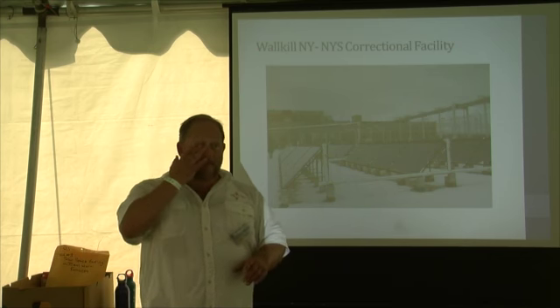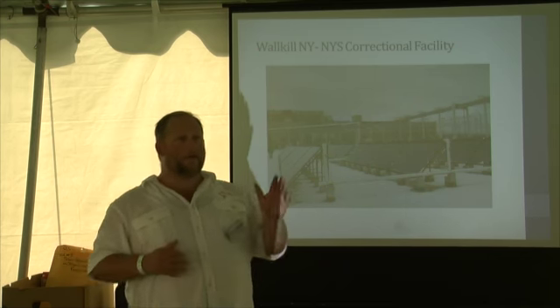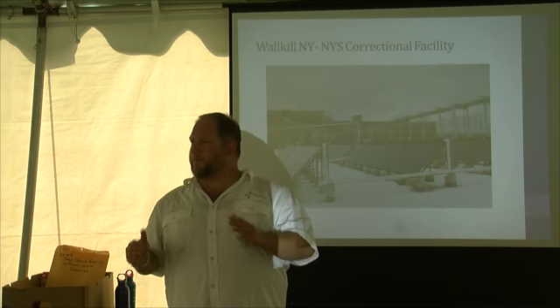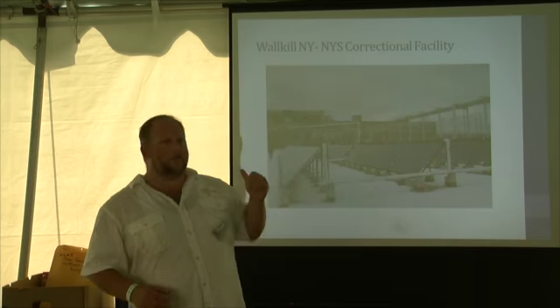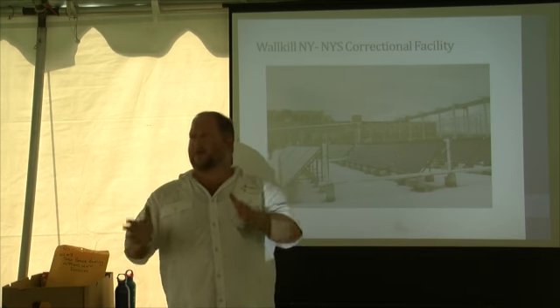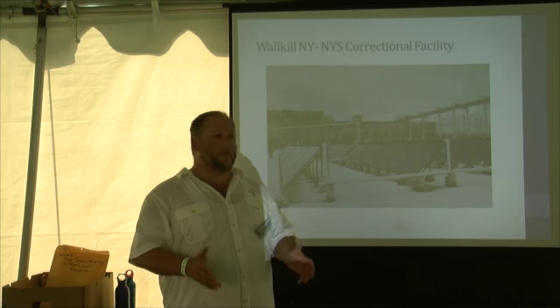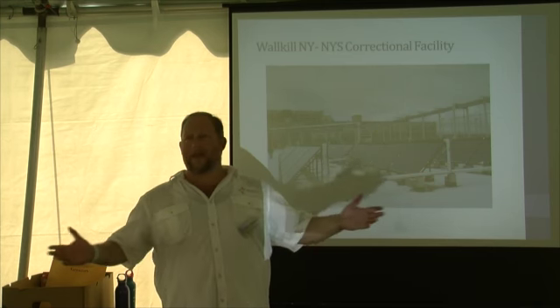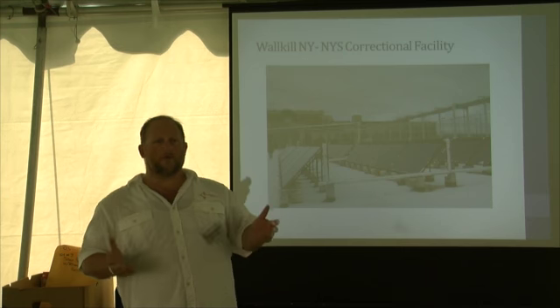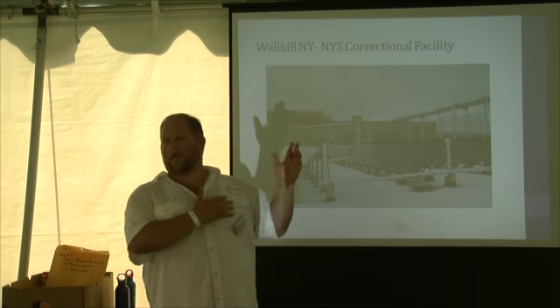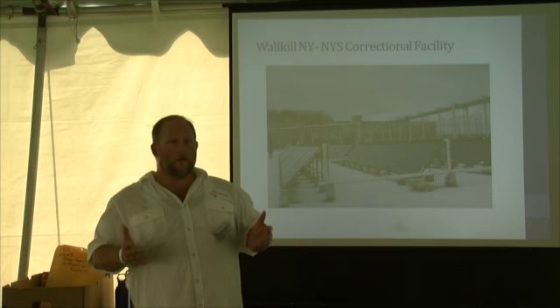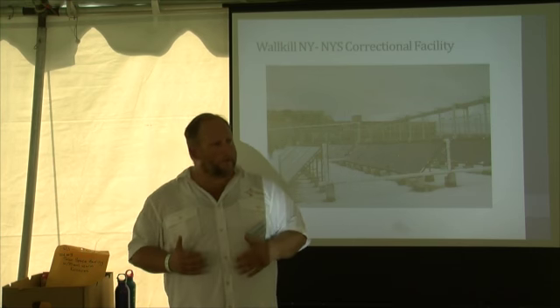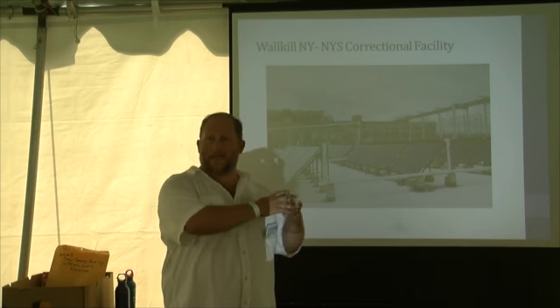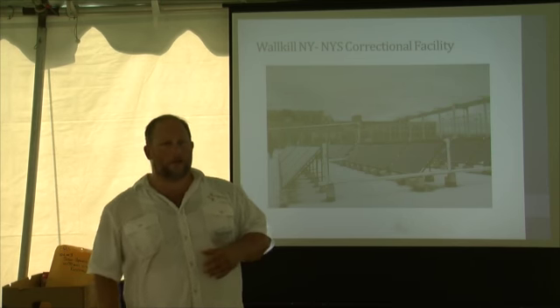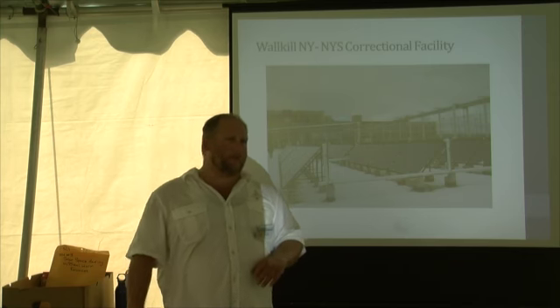The reason is we looked at the load profile—remember, we have to look at consumption versus production. It turned out they were using more BTUs during the solar day than we were producing. So we scratched the storage tank, which was about $10,000, right off the budget because there was no need for it. They're consuming more than we're producing, meaning they're taking every single BTU out of these collectors all day, and the collectors are constantly playing catch up.